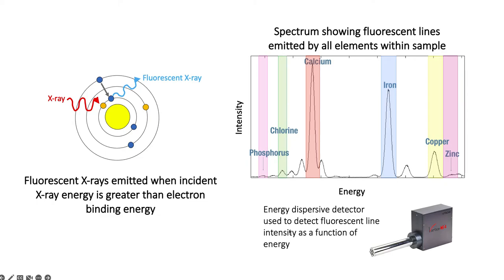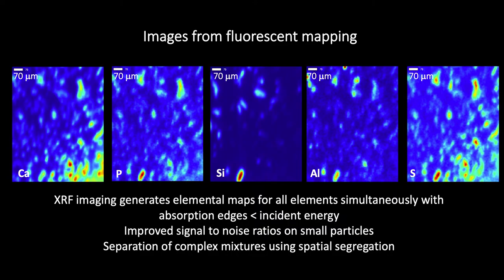Fluorescent x-rays are emitted when the incident x-ray energy is greater than the electron binding energy for an atom. The x-ray comes in and ejects a core level electron, leaving behind a core hole. This configuration is unstable, so an electron with higher energy falls into that core hole, giving off a fluorescent x-ray. Importantly, that fluorescent x-ray energy is characteristic of the element, so we can measure the intensity of x-rays as a function of their energy using an energy dispersive detector to obtain elemental composition. X-ray fluorescence imaging generates elemental maps for all elements in the sample simultaneously, as long as those elements have absorption energies less than the incident energy of the incoming x-ray beam.